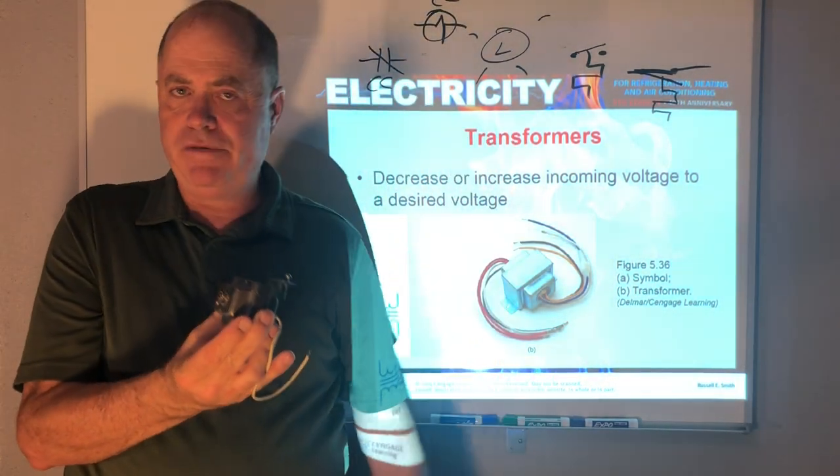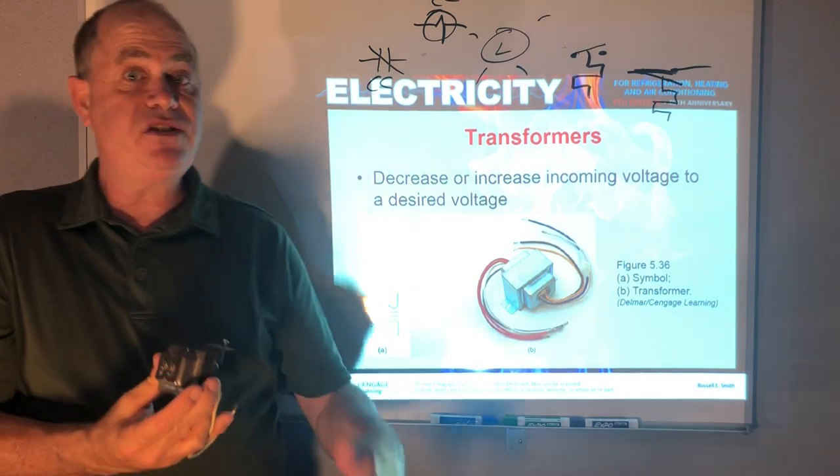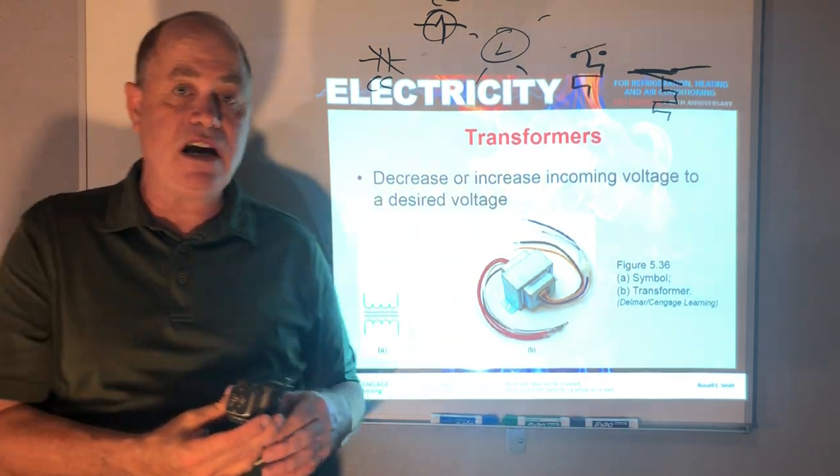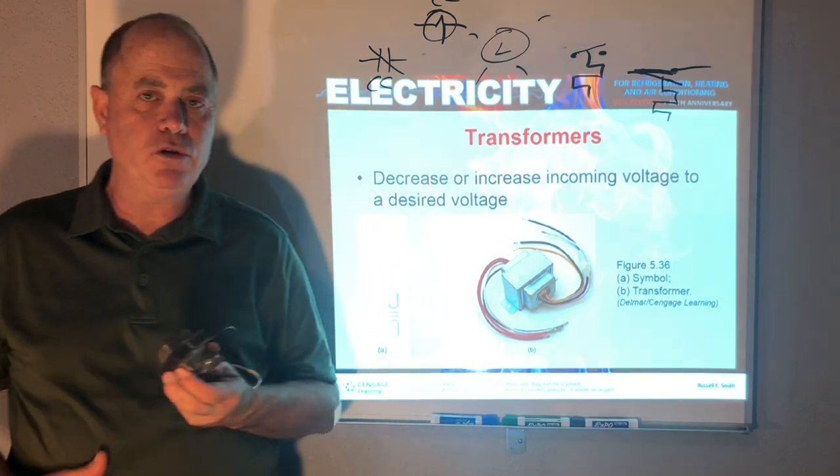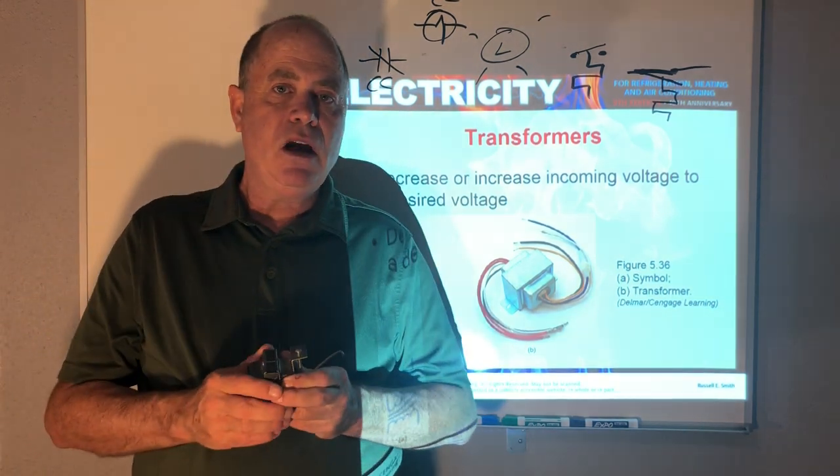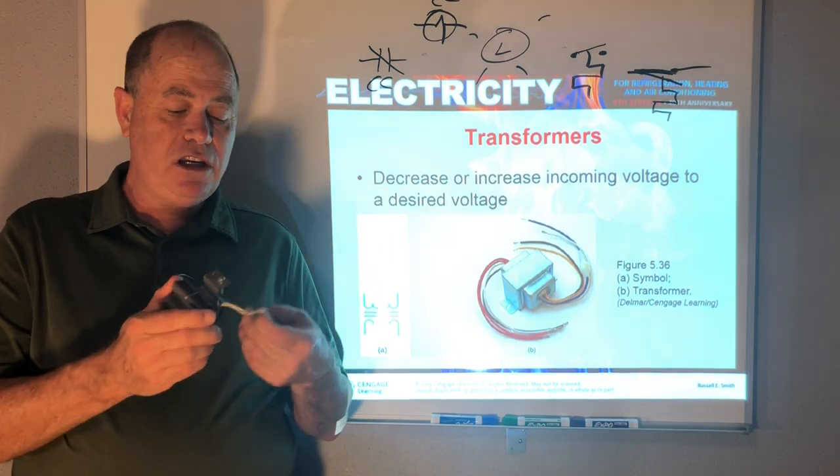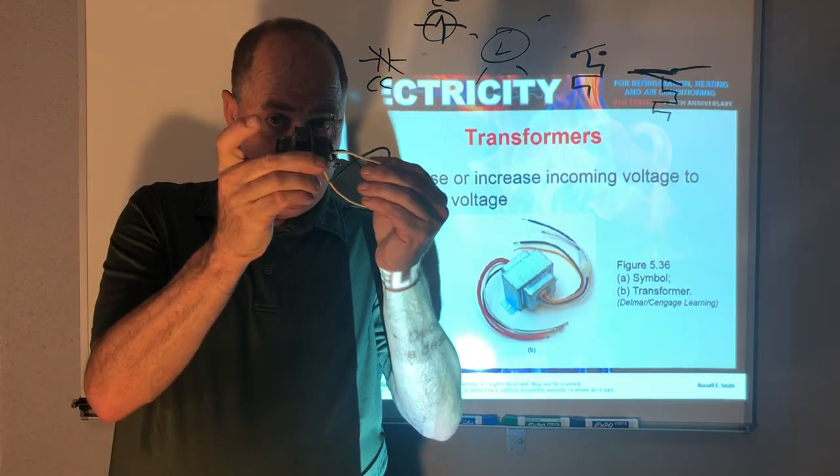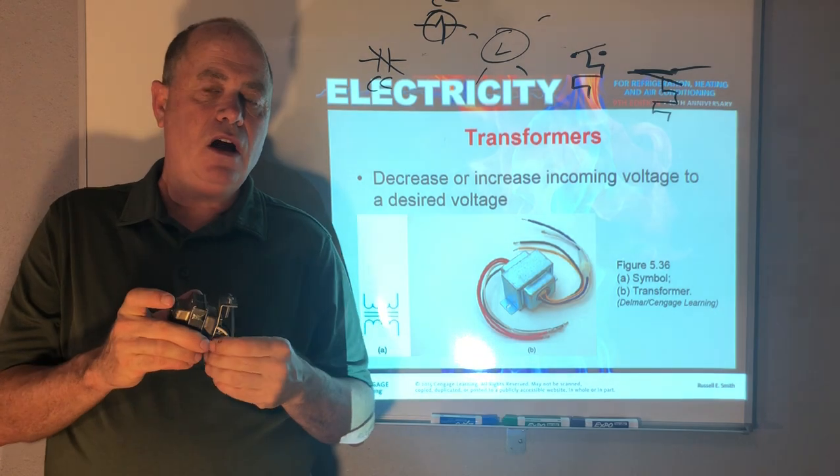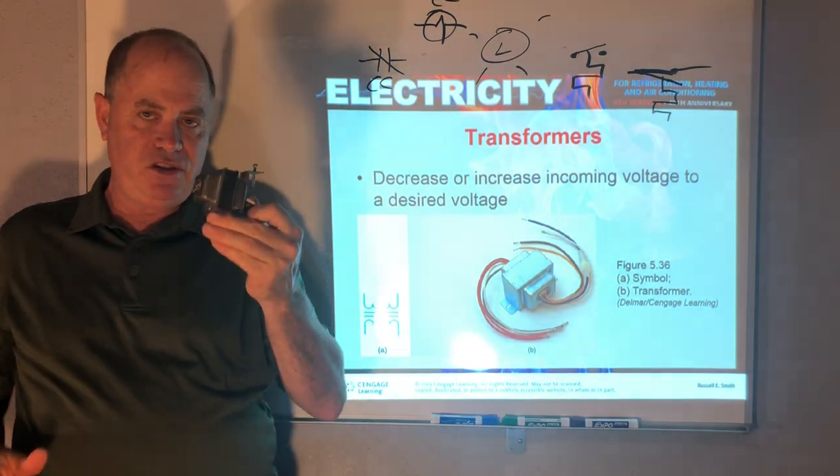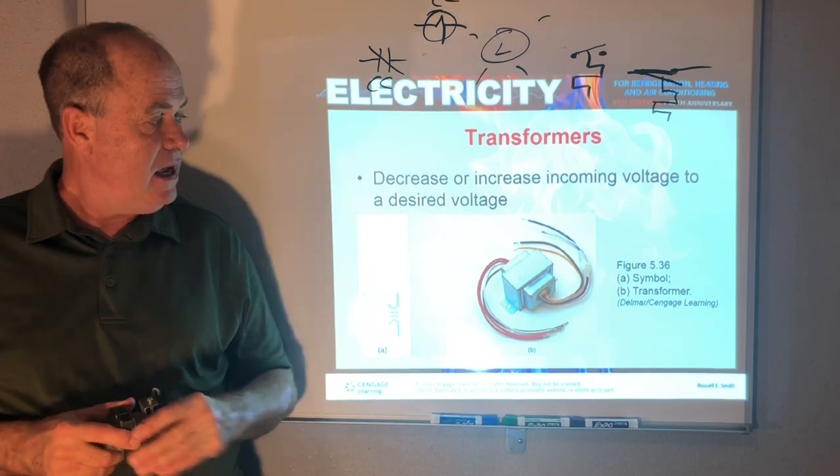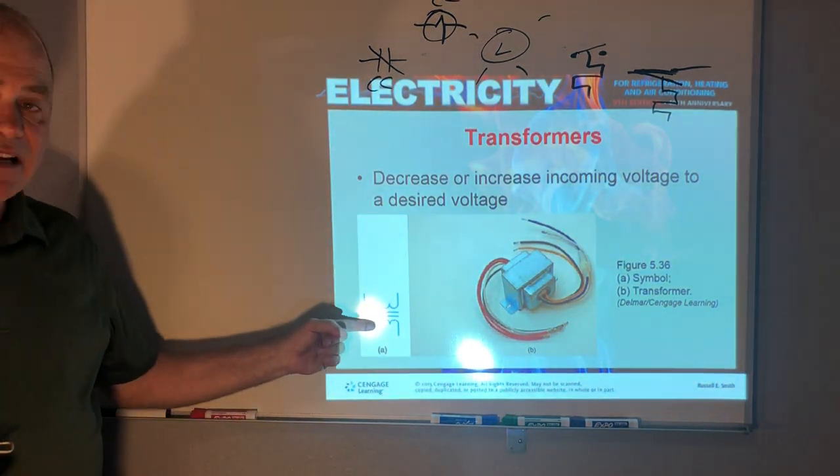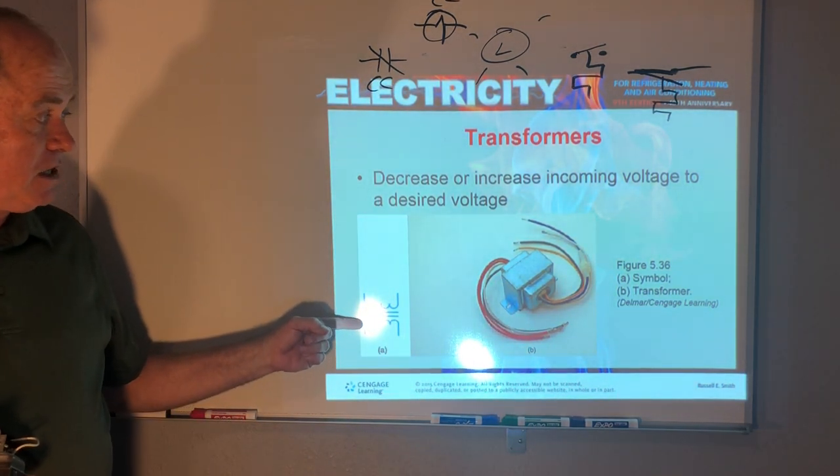And we always have transformers all around the city dropping the power down to voltage lower and lower, but in air conditioning, the control voltage that's most common is 24 volts. So we usually drop it down from, let's say 115 volts in this case, or 230 volts down to 24 volts. And you see a lot of these type of transformers in our industry.